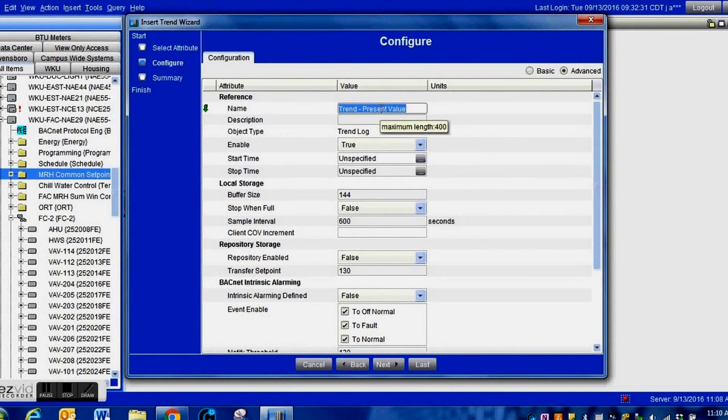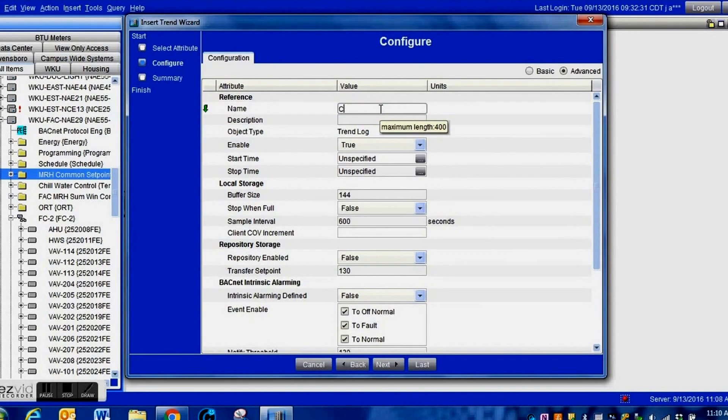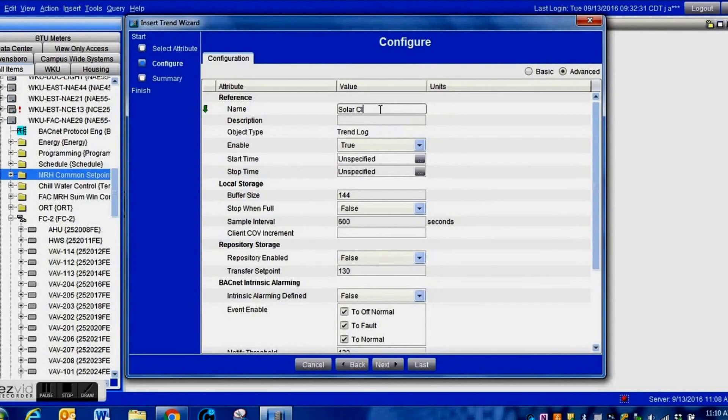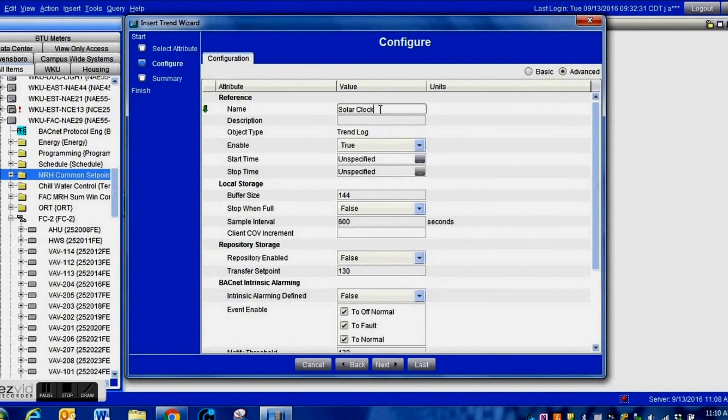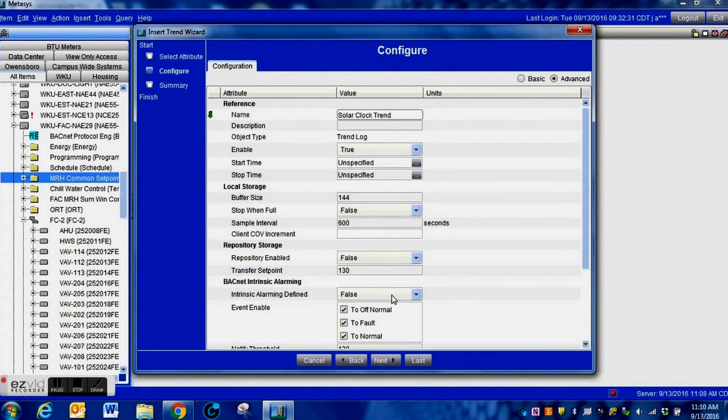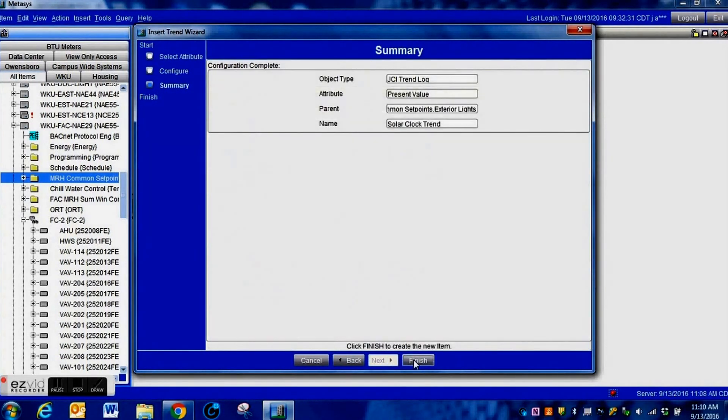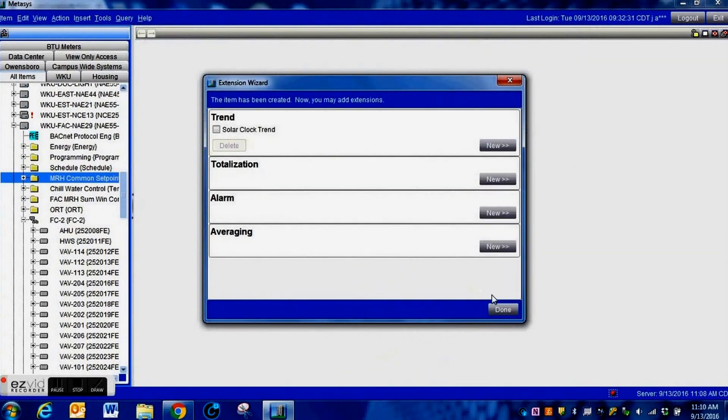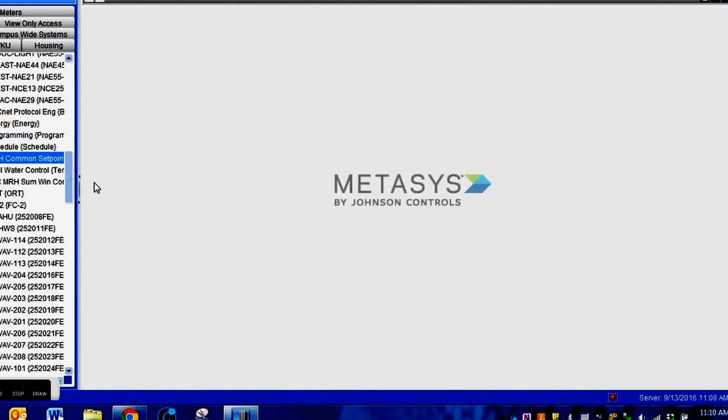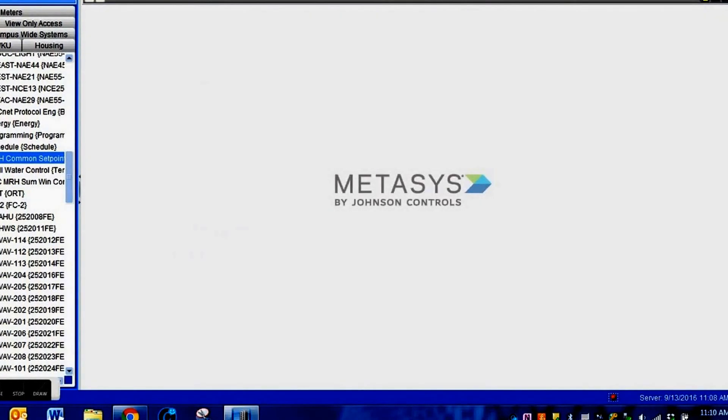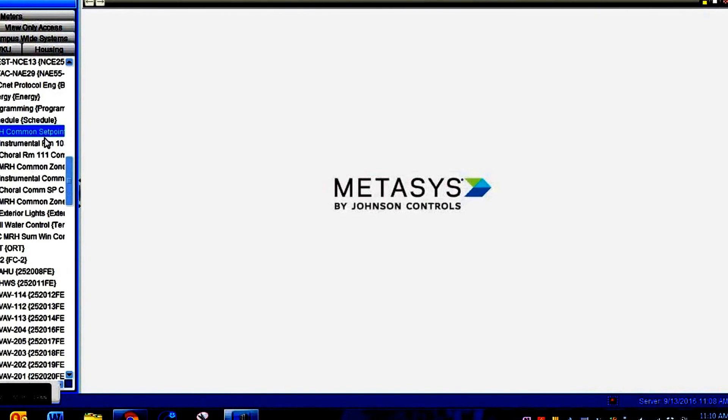I would recommend that you set a trend up on this so you can see what the system is doing, exactly when the solar clock is changing, and if you need to make any adjustments. Give it a simple generic name related to that solar clock. That is the first of the two objects we need to create. You can see our solar clock down here at the bottom of this list.